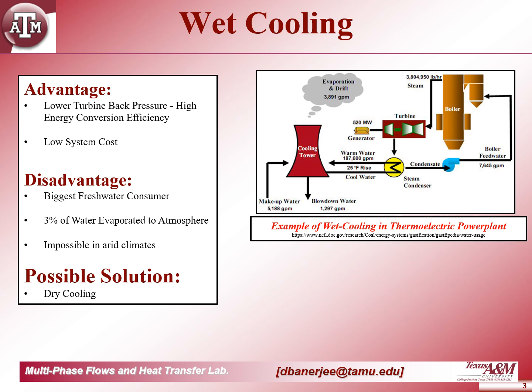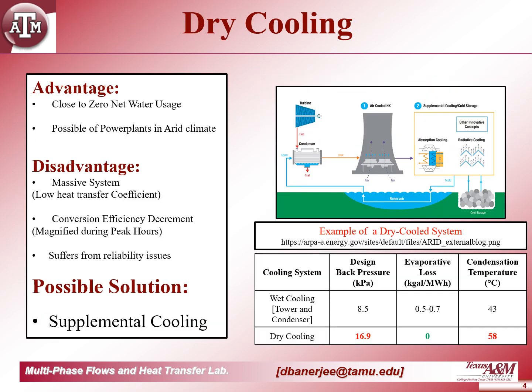Wet cooling is predominantly used due to its higher efficiency than dry cooling, but it's not practical in arid climates. To avoid the difficulty of using wet cooling in arid regions, dry cooling can be used. However, due to poor heat transfer properties of air, it is not a reliable option. Hence, supplemental cooling is necessary to implement dry cooling in arid climates.